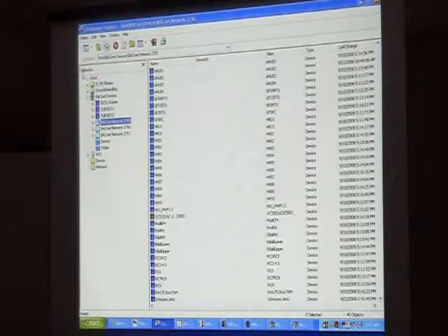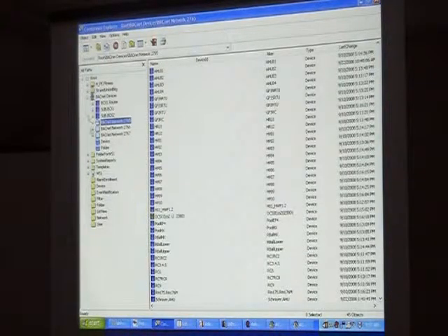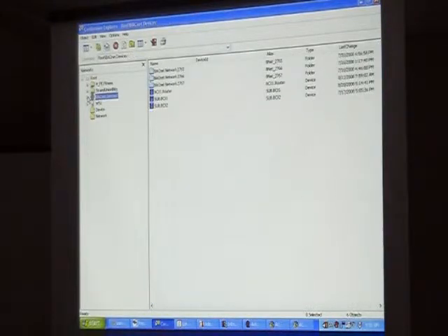Now we're looking at network views. Click it again, gives you folder view. Click it again, gives you templates view. You see how now I don't even get to see the BCX or anything. BACnet devices only, and then all paths. I use all paths because I want to see everything that's going on. So if you need to change, typically what Bill leaves it at is your network view, okay? There's a lot of things you can't see in your network view that you're going to end up needing for troubleshooting, so I always leave it on all paths. If you have to go to all paths, all you got to do is go to that button. Click it till it goes to all paths.